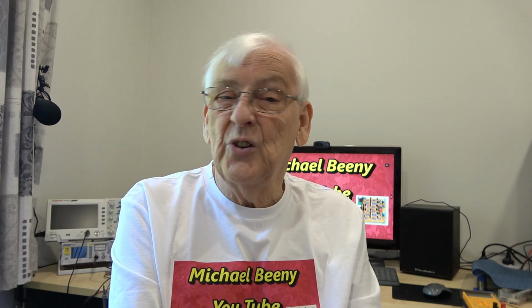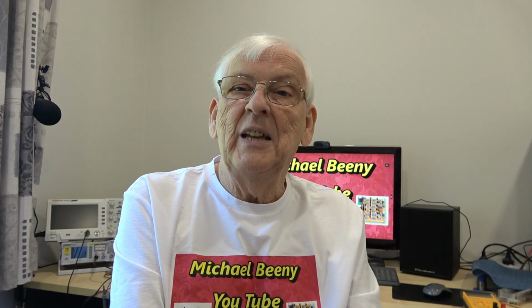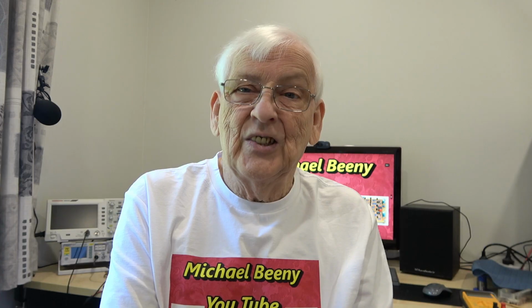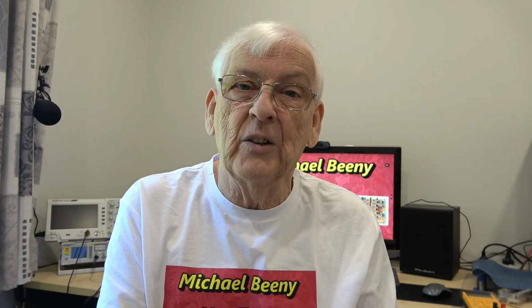Will you need one of these modules? It depends on many things -- there's no single rule, since I've used amplifiers of such power without them before. But we're advantaged here by having 240 volts. If you're in a country using 110, 120 volts or even less, the current will be more or less double, because the voltage is lower -- not strictly accurate, but you get the meaning. So the current flowing when you first turn on such a system with 120 volts would be considerable, and you'd either need a larger fuse, which is counterproductive since the fuse is there to protect against something drawing lots of amps, or you use one of these little modules.